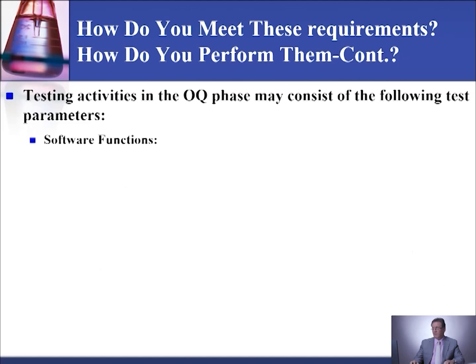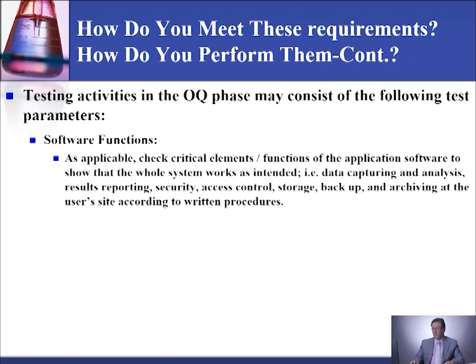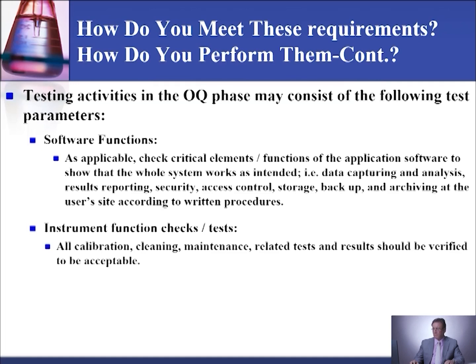What are the testing activities that you need to do for the OQ phase? They are as follows. First, you need to check the software functions. As applicable, check critical elements and functions of the application software to show that the whole system works as intended. For example, data capture and analysis, result reporting, security, access control, storage, backup, and archiving at the user site according to written procedures. Also, you need to check the instrument function checks or tests, as all calibrations, cleaning, maintenance, related tests and results should be verified to be acceptable.